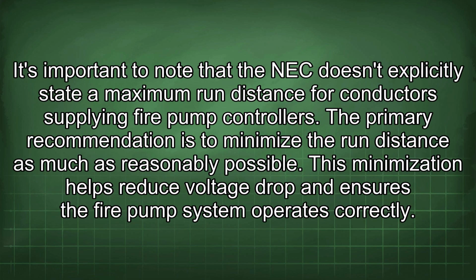It's important to note that the NEC doesn't explicitly state a maximum run distance for conductors supplying fire pump controllers. The primary recommendation is to minimize the run distance as much as reasonably possible. This minimization helps reduce voltage drop and ensures the fire pump system operates correctly.